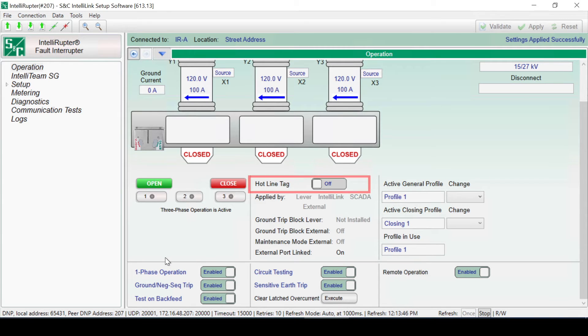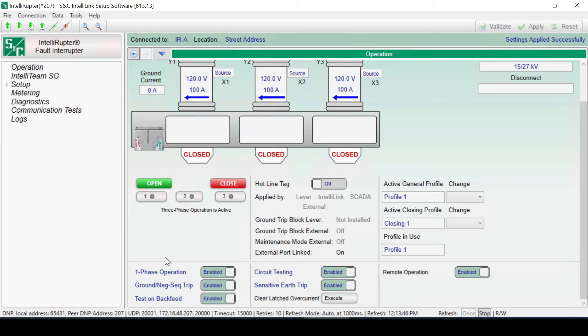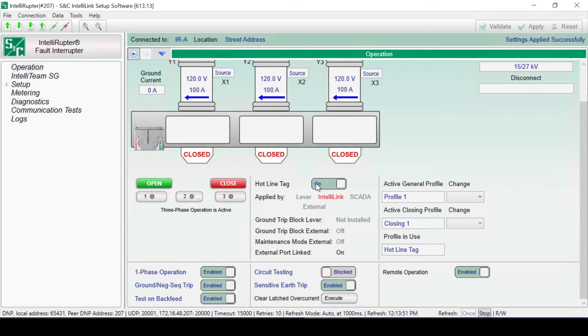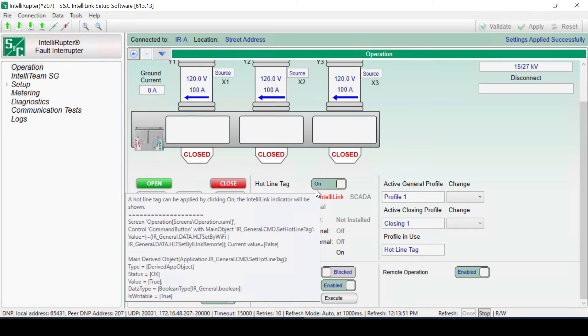When a hotline tag is enabled, the fault interrupter will not close. If applied when the fault interrupter is closed, the interrupter can be opened but not closed while the hotline tag is in place. A hotline tag can be applied through the software by clicking the hotline tag slide control to On.